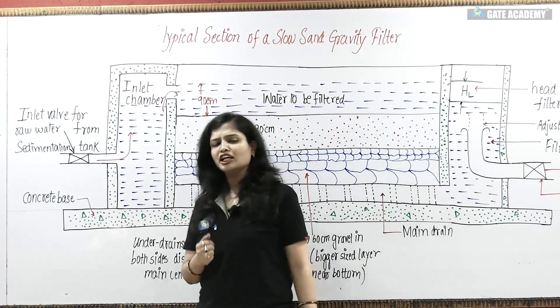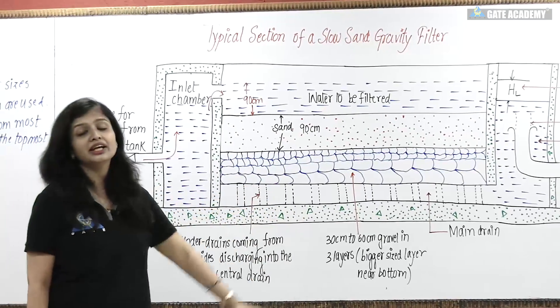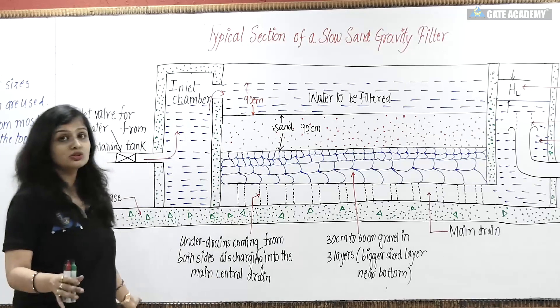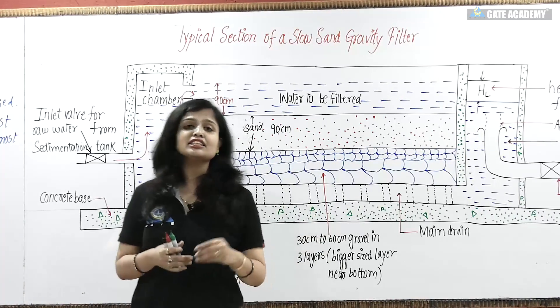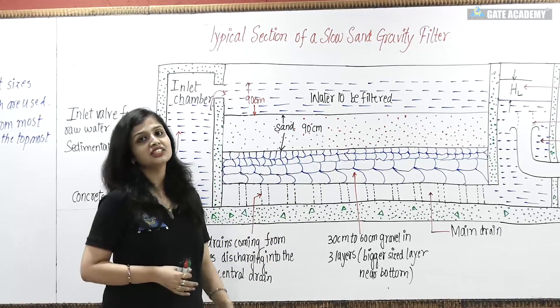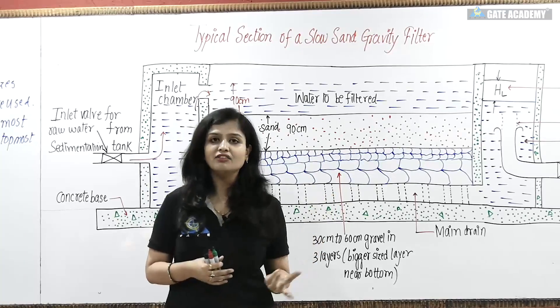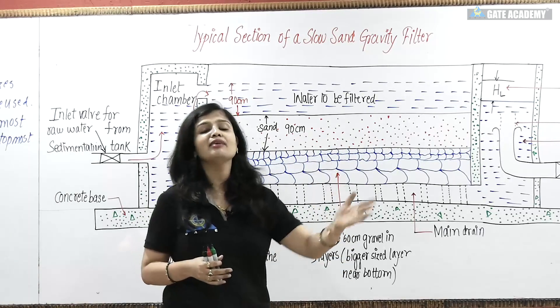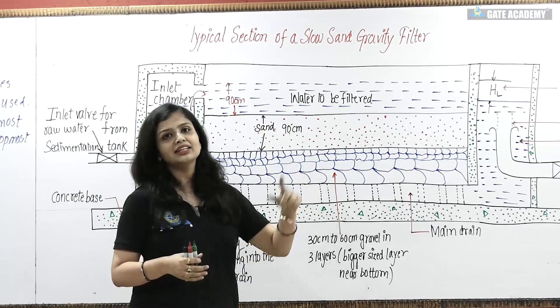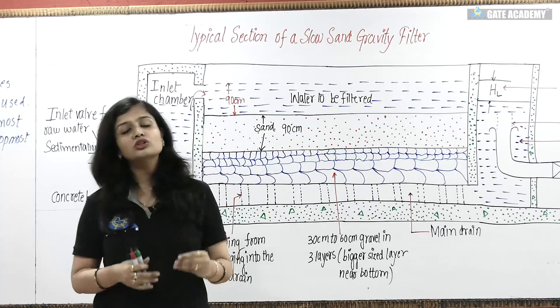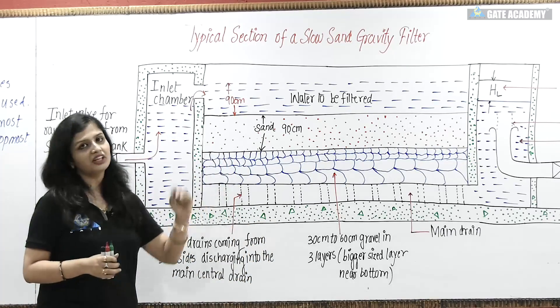The bacteria removal efficiencies are high, but the drawback is that the area required is 100 to 2000 meters square — you can think about how much area is needed to set up slow sand gravity filters. The rate of water supply per hour per meter square area is less than 30 times compared to rapid sand gravity filters. If you need to supply a large quantity of water and don't have the large land area required, we don't use slow sand gravity filters.